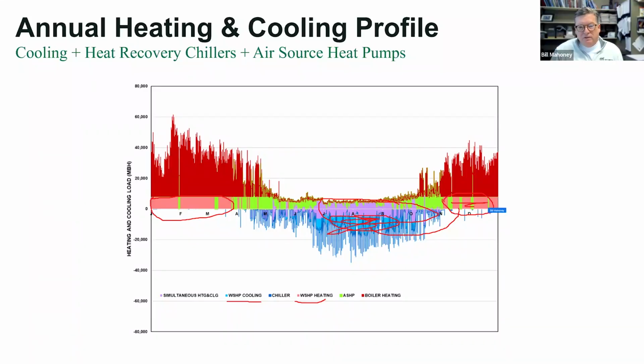So we have to make up the difference. And that is first made up with air source heat pumps, which is the green areas here, right in the shoulders of the heating to cooling season. We intentionally run in that period because that's when the ambient temperatures won't be so cold, so we can make our design temperature for the hot water supply going out to the campus. And it's a pretty good COP if it's only 20, 30 degrees outside. And then in the dead of winter, we just can't do it all. And we're left with these big areas here of the dark red, and that's just the supplemental heat.